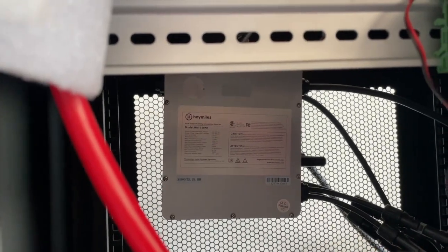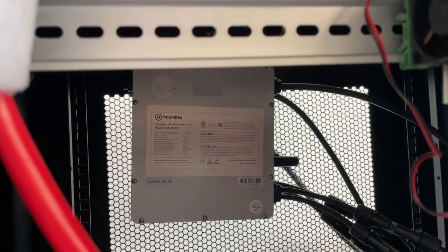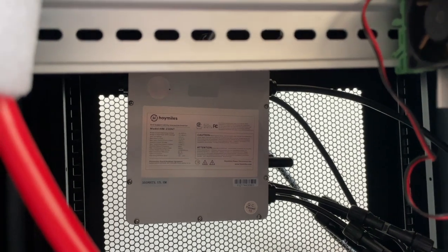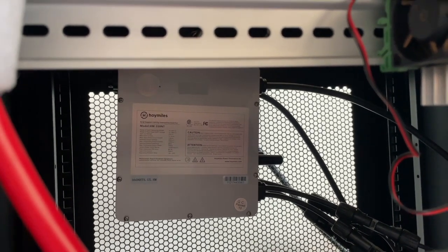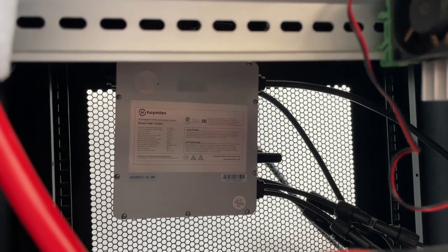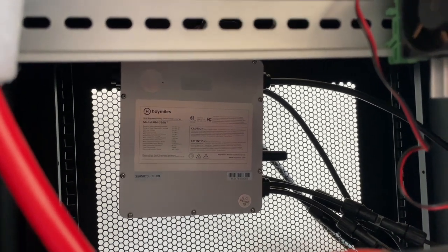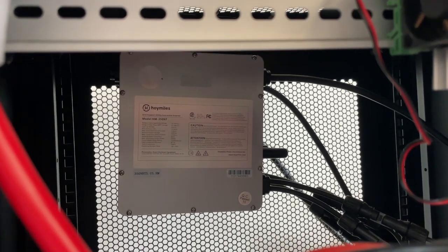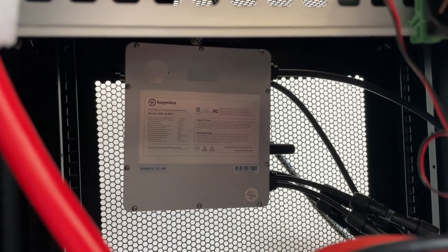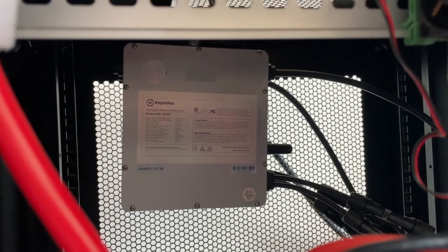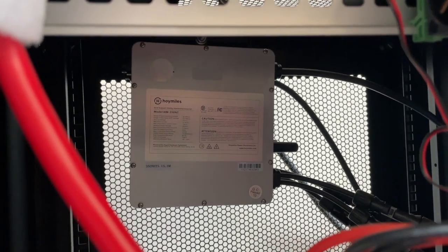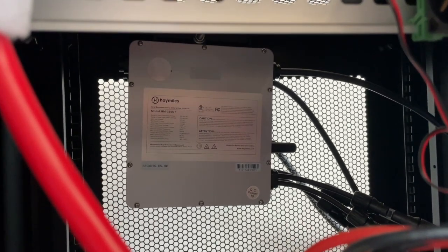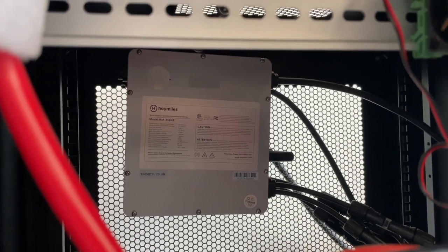I have tested it running in parallel with my Enphase IQ Battery 3T. It works fine once you get the 3T up and running - you can add these to it. But if you transfer over from grid to battery, the Enphase system drops the Hoymiles inverters.